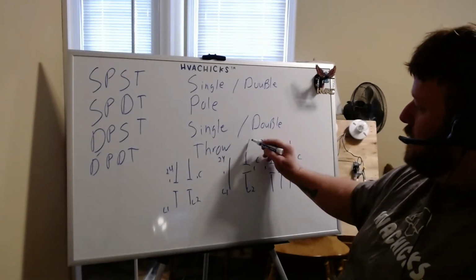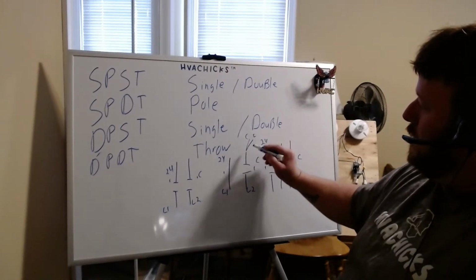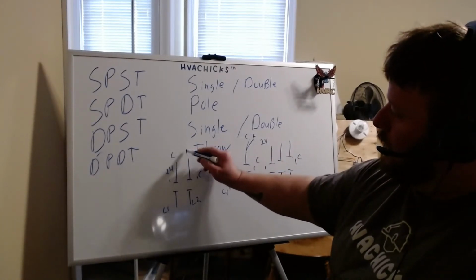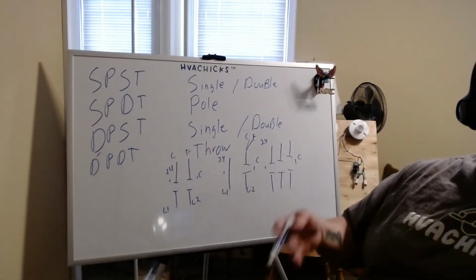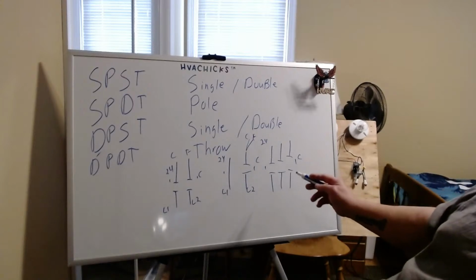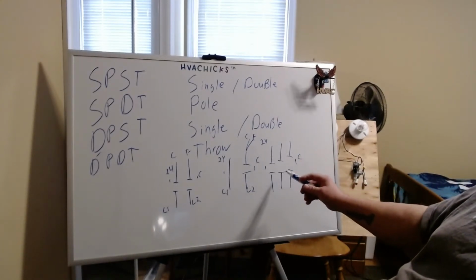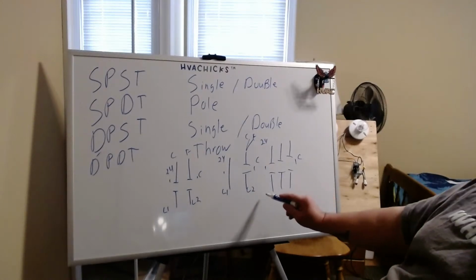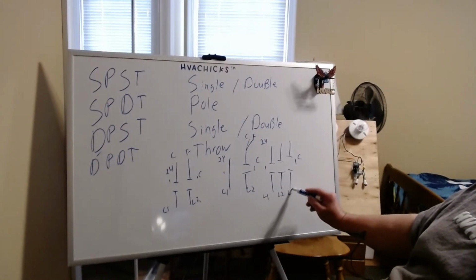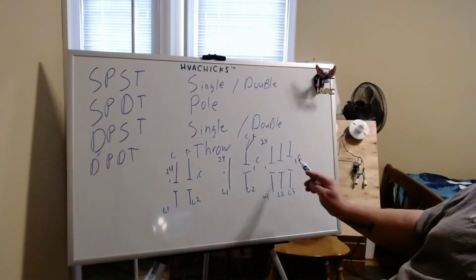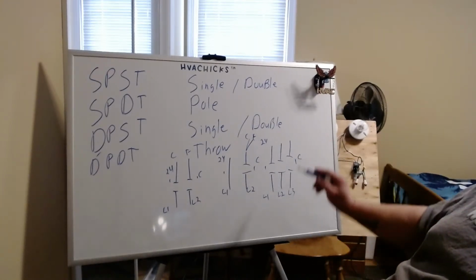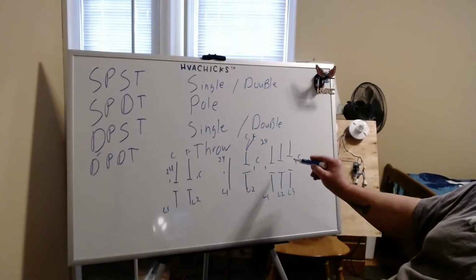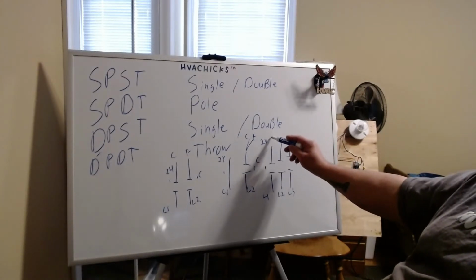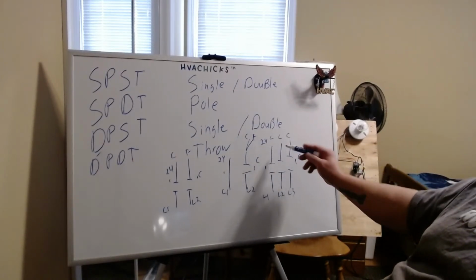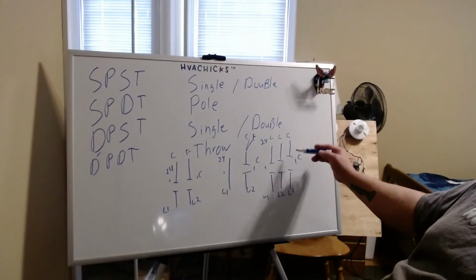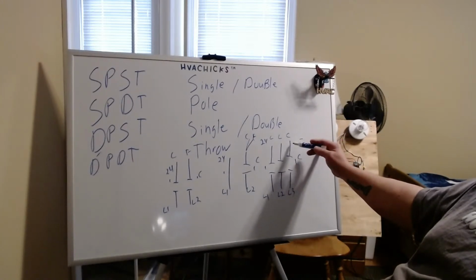Even though your compressor and your fan come off of it, you're still throwing that circuit. Now this here, 1, 2, 3. So you have L1, L2, L3. Triple pole, triple throw. This is more of your commercial or three-phase systems. So you'll have compressor, compressor, compressor lines coming in. Your blower motor may have its own contactor with its 3 lines.